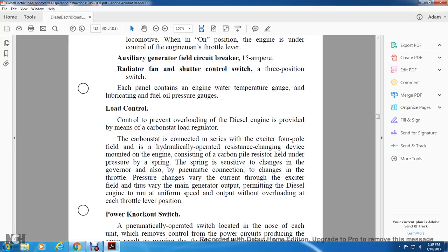Control to prevent overloading of the diesel engine is provided by means of the load regulator, connected with the exciter of the four-pole field. A hydraulically operated resistance change device mounted on the engine consists of a carbon pile resistor held under pressure by the spring.